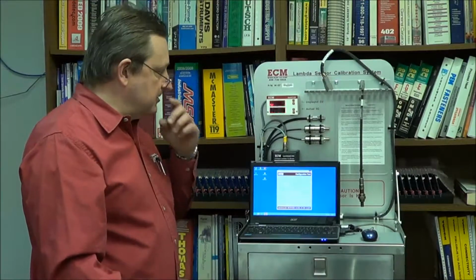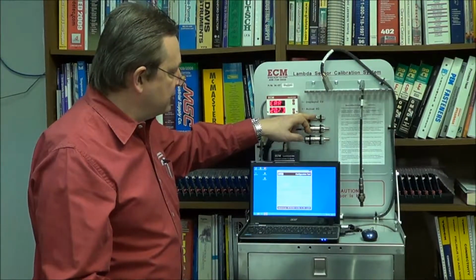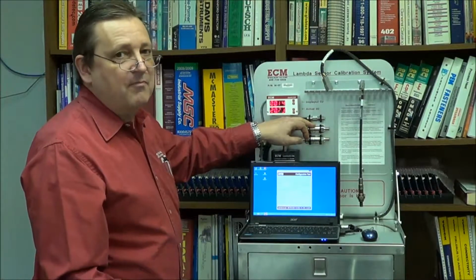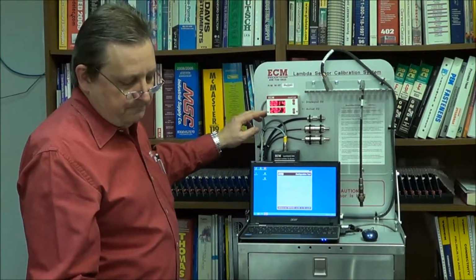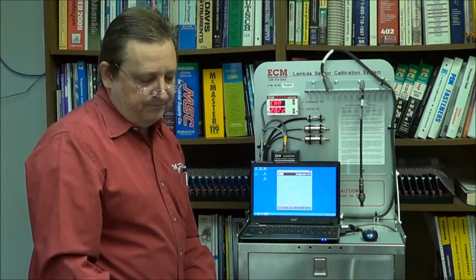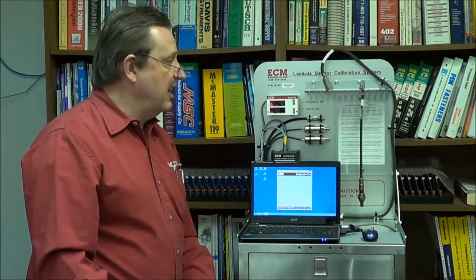With the ECM calibration system, humidity is measured by the BaroCAN module, which uses two sensors, a humidity/temperature sensor and a pressure sensor. Math is then performed in the BaroCAN module, resulting in a percentage O2 in air that is displayed on the lower display. This number should be 20.945 if there was no humidity in this room. Typically, you'll see a 20.7 number. The sensors used by the BaroCAN are calibrated by ECM, have a calibration tag on them, and can be periodically sent back to ECM for recalibration.